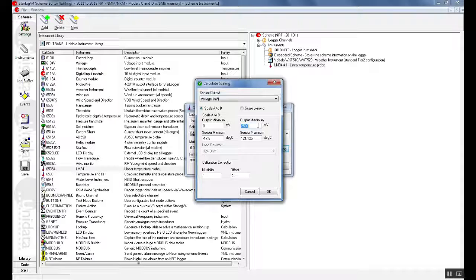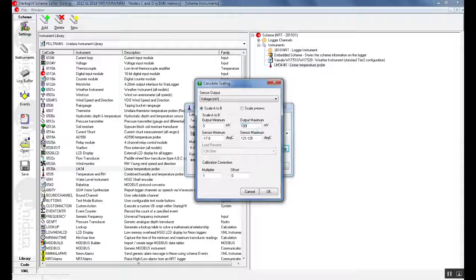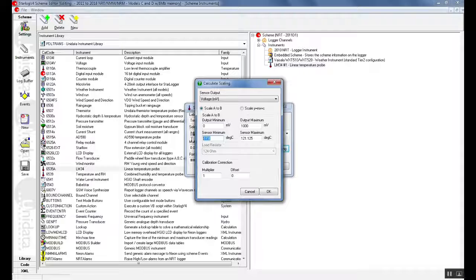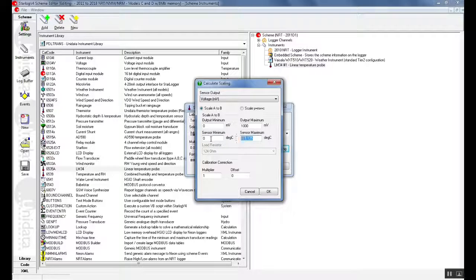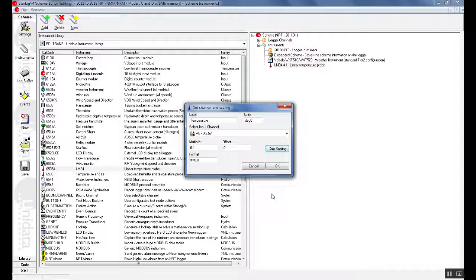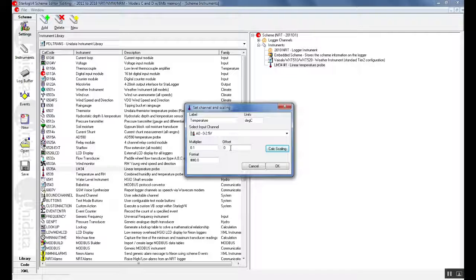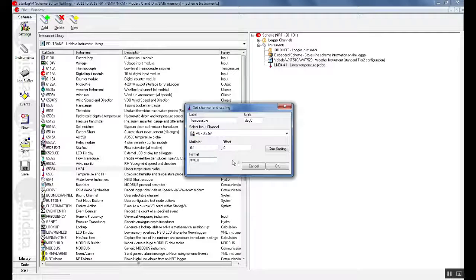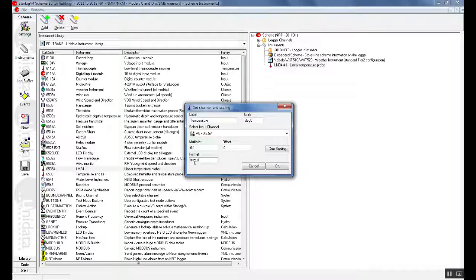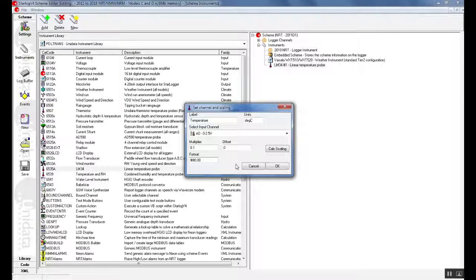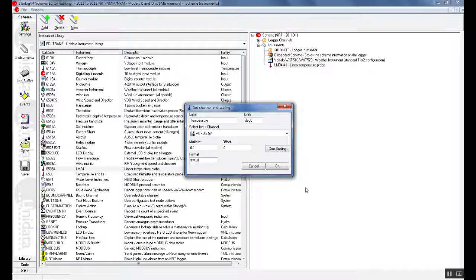For example our temperature sensor might be only a 0 to 1 volt input so we could change this to 0 to 1 volt or 1000 millivolts. We could also change our sensor minimum and maximum. For example for 0 volts we might have 0 degrees Celsius and for 1 volt we might have 100 degrees Celsius. Once we have changed this we can click OK and our multiplier and offset will be automatically changed according to the scaling we have just done. The format allows us to determine how many decimal places we require for our recording of our data channel. For example for 100 degrees Celsius we might want 100.0 or 100.1 degrees Celsius. If we want more resolution we can add an extra 0 and we might get 100.12 degrees Celsius depending on the accuracy of the instrument. Once we are happy with this we can click OK.